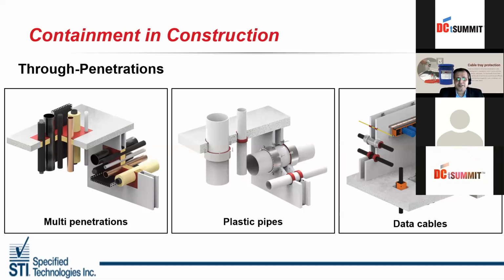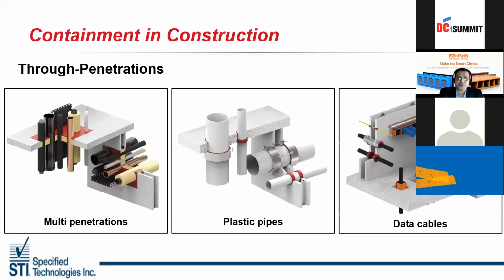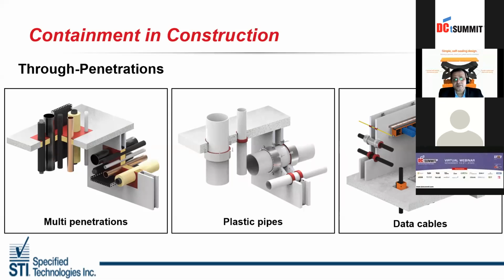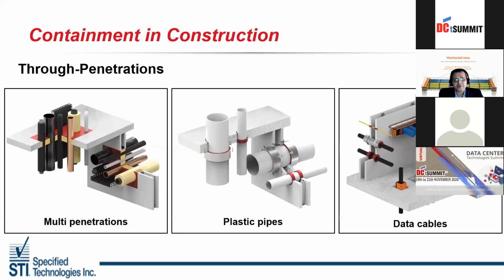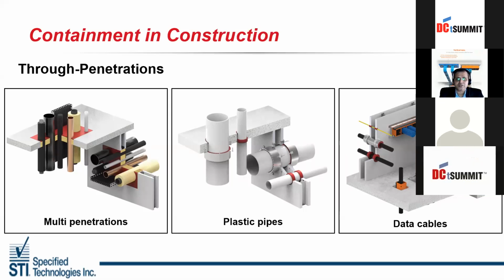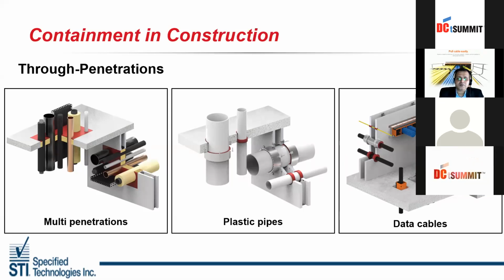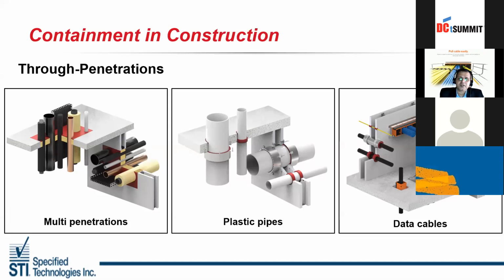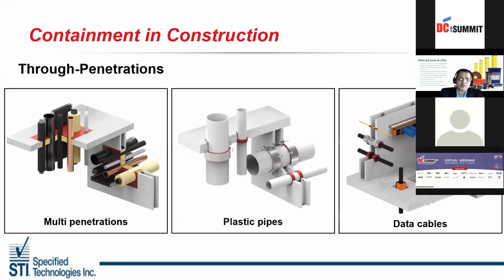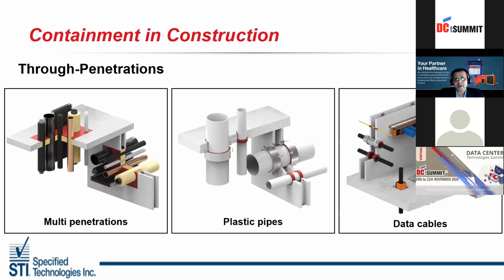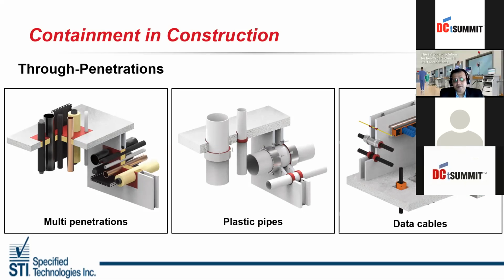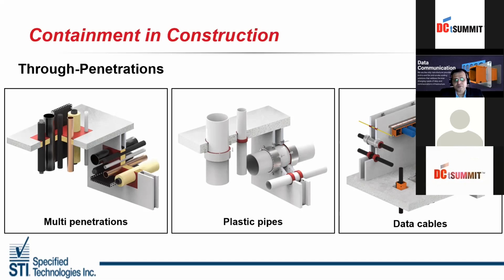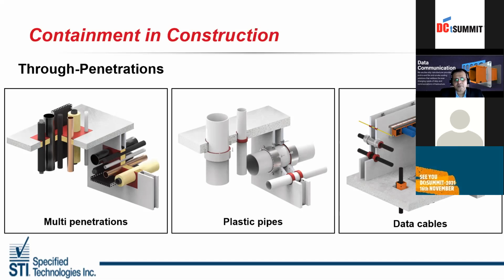Towards your last right-hand side are the data cables, which are the most important part in a data center, wherever there are multiple changes happening in the cables. And every 6 months or so, you upgrade from Cat 5, Cat 6 or Cat 8, whatever cables you're changing. So every time you change the cables, you need to have the fire sealant guys coming in and changing the sealant. So we have those areas also wherein a fire sealant guy does not have to come, and it can be easily changed by a cable guy themselves. I'll come to that part. Slowly, when we proceed further, we'll see the product data sheets also.